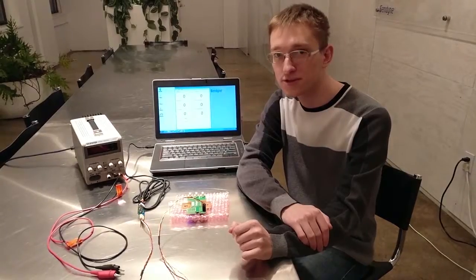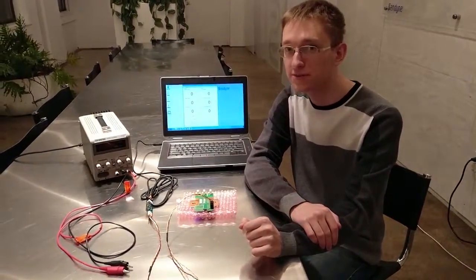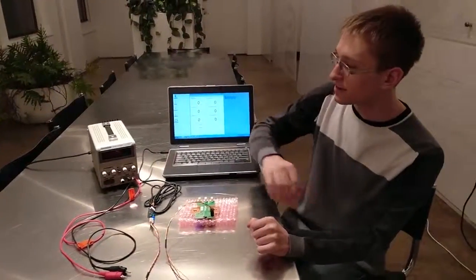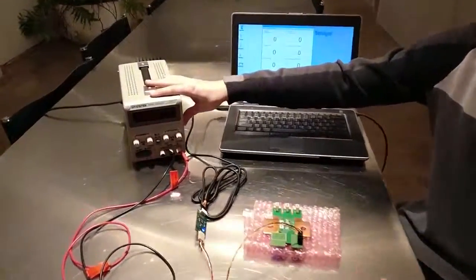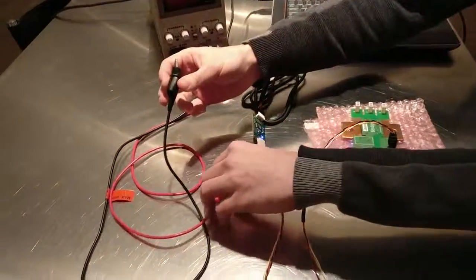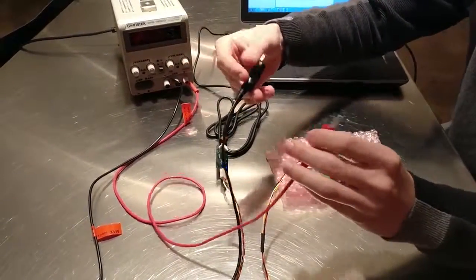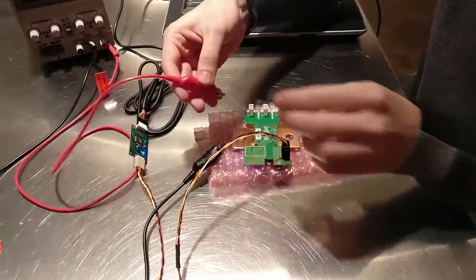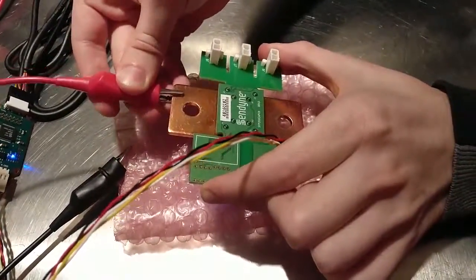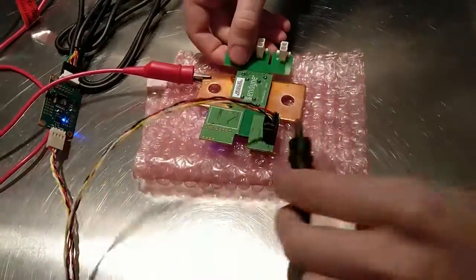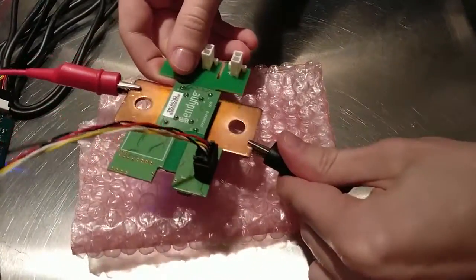Now that we have the SFP200 connected to the host, we'll demonstrate its current measurement functionality. We have our current source with positive and negative terminals. We connect the positive to the positive side of the shunt and the negative to the negative side of the shunt.